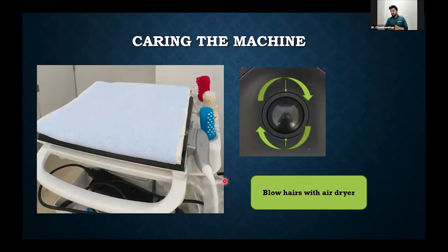So again, whenever it is a hospital setup, it's not just about diagnosis and leaving the machine like that. You have to take care of the machine. Your mentors or you may have invested a lot in this. If I say an USG machine costs somewhere between 15 to 35, sometimes 40, 45 lakhs together. So you have to take care of the machine so that whatever you have invested should come back also. Here you can see I have covered all these probes with the help of baby socks so that it will prevent a lot of wear and tear on the piezoelectric crystals there.